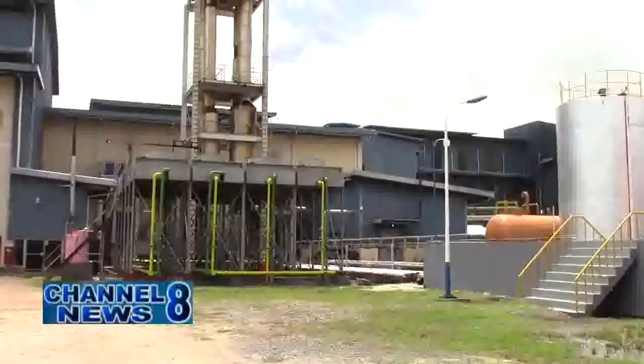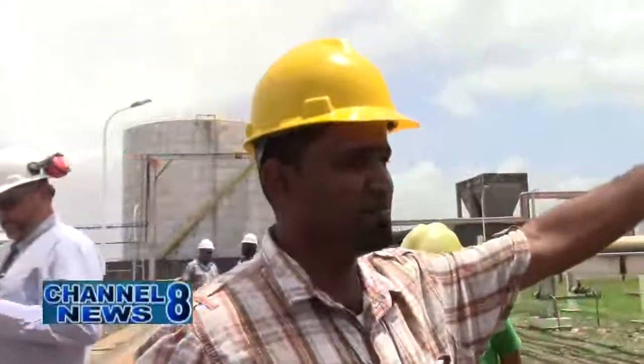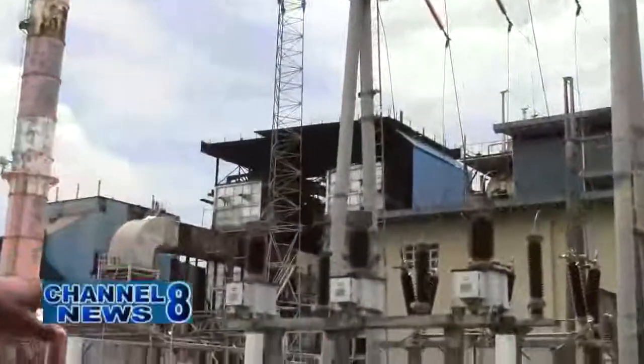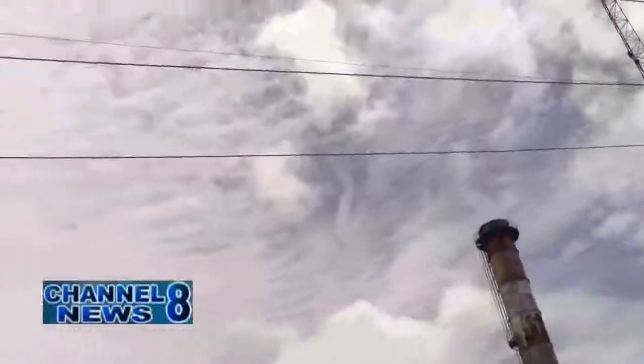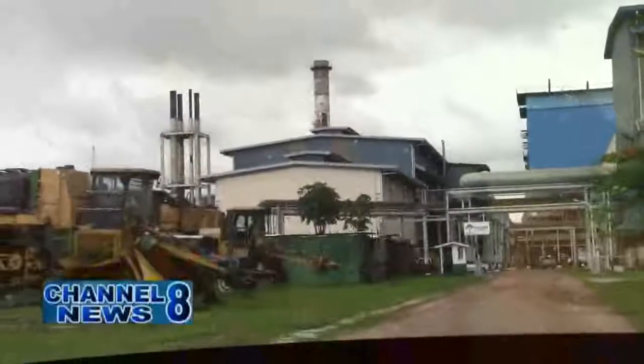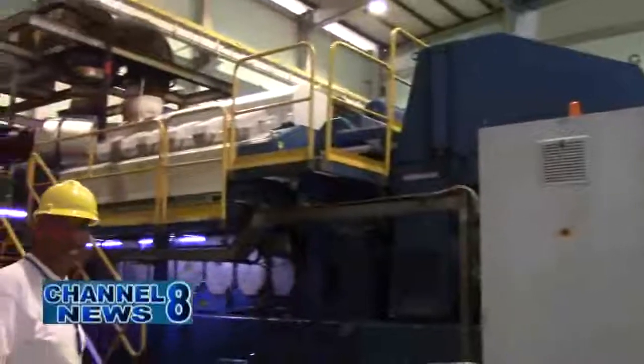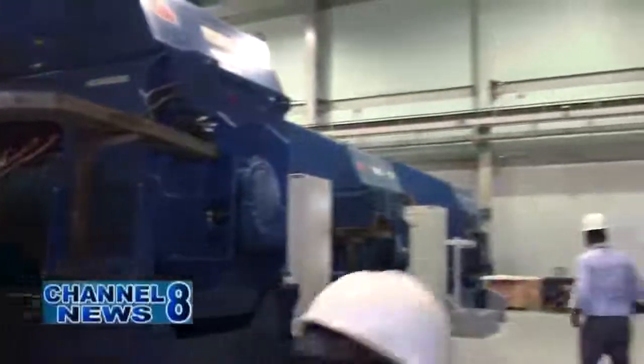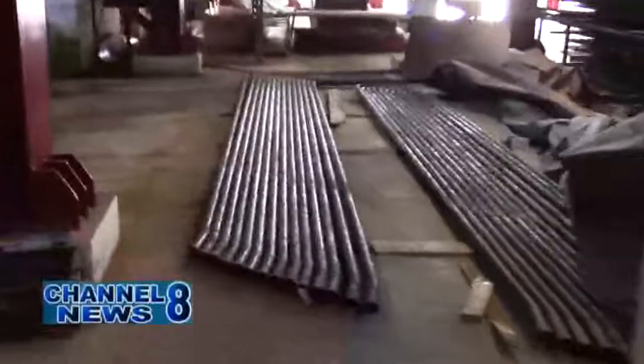Mr. Singh, the instrument and electrical engineer, shared how SEI supplies GPL with electricity. Basically, what we are looking at here is our interconnection with GPL, where we generate 30 kV, step up to 69 kV for transmission purposes, and it goes out to GPL for distribution purposes. That's basically our 69 kV distribution and interconnection with GPL. The Skeldon Energy Inc. has been providing GPL with electricity for a number of years. Last year, 2017, SEI produced 90.7 GWh, of which 74.5 GWh were sent out and distributed to the GPL grid, representing approximately 9.5% of GPL's total distributed energy.